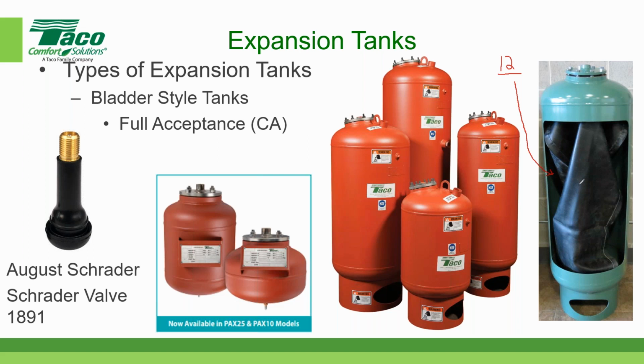So ask the question again, because I think I only answered half the question. The question was, what happens to the air inside a full expansion tank? There is nothing on the inside. There's no air and no water on the inside of the bladder, assuming that nothing has leaked, because we pressurize them to 12 psig before we ship them from the factory, and that ensures that there's no air or water inside the bladder.